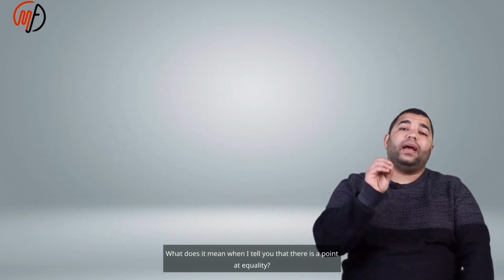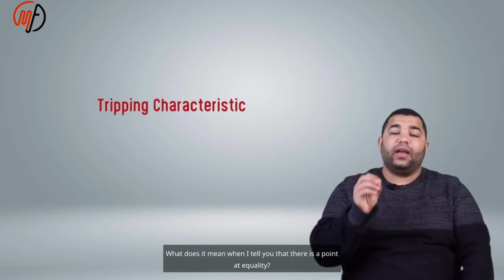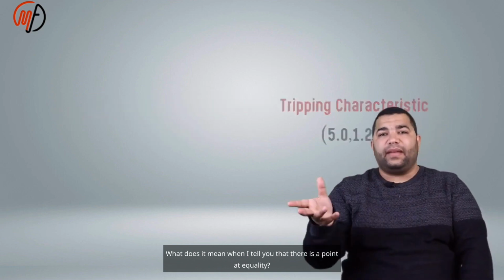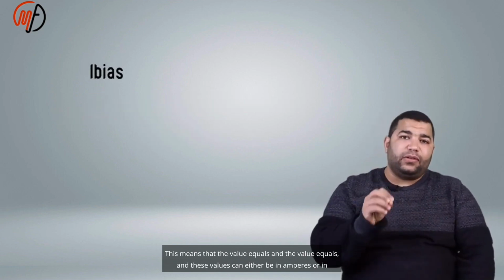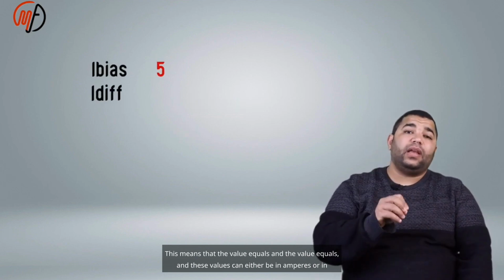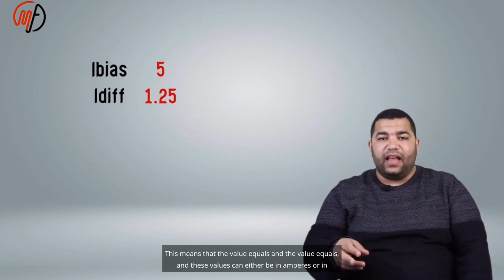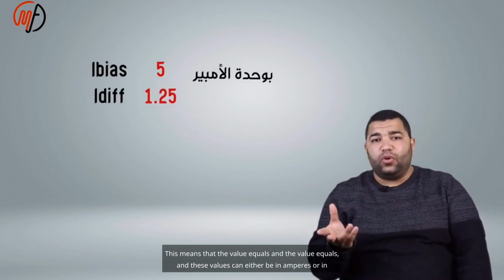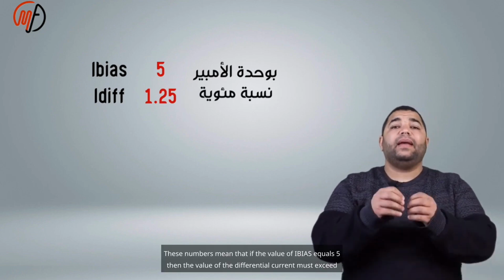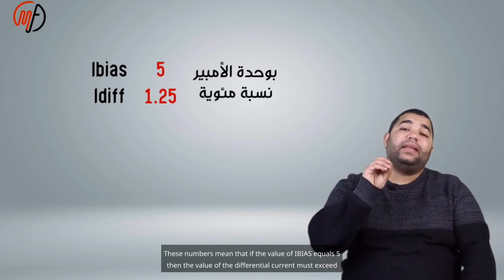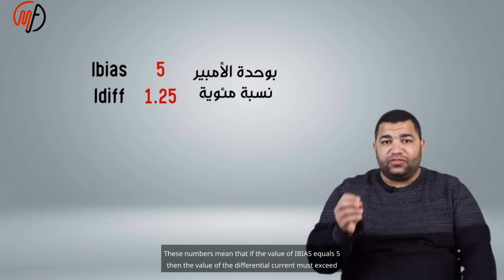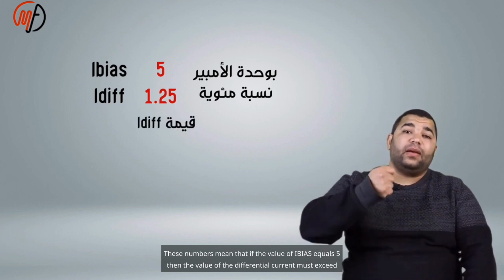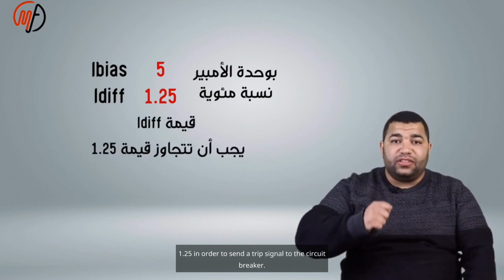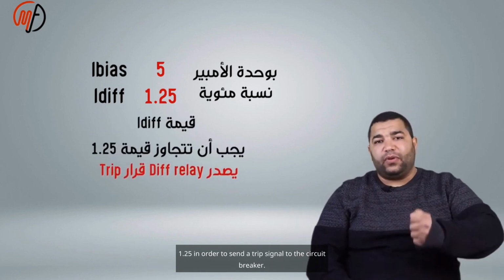What does it mean when I tell you that there is a point at equality? This means that the values are equal, and these values can be either in amperes or in percentage. These numbers mean that if the value of I bias equals 5, then the value of the differential current must exceed 1.25 in order to send a trip signal to the circuit breaker.